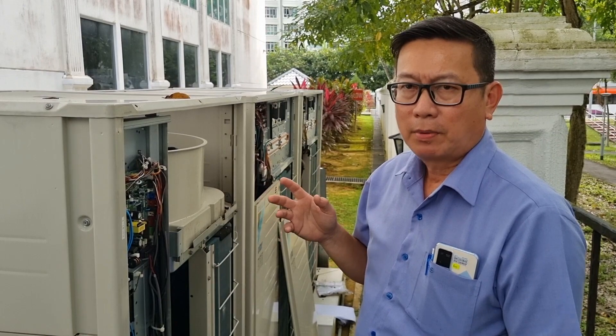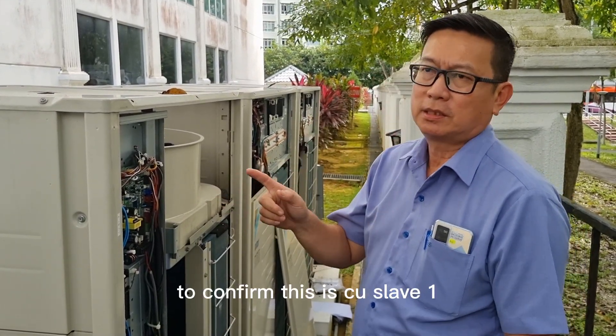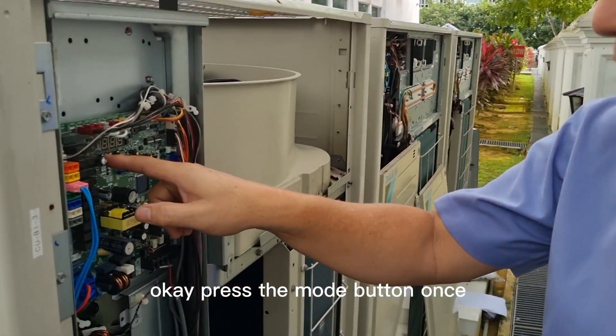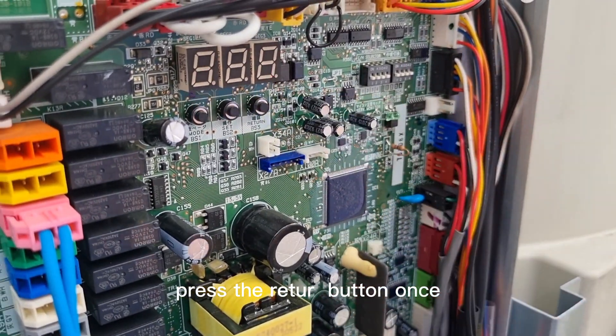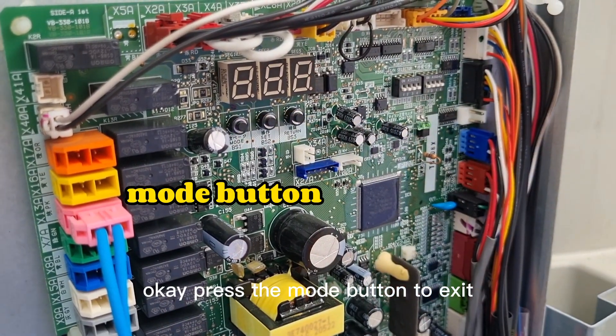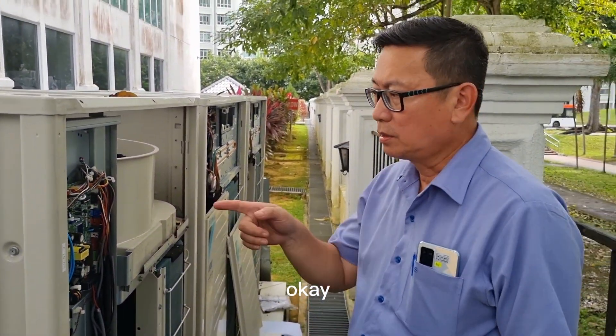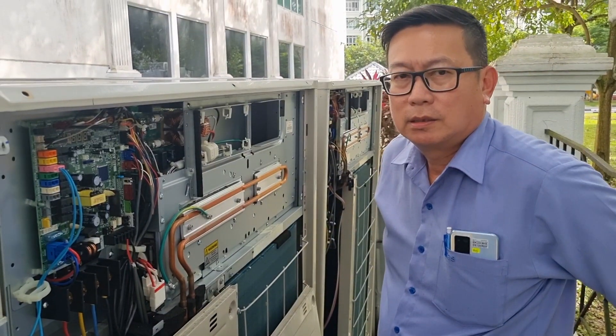That means Slave unit one has a power supply or communication error. Now we check to confirm this is Slave one. Press the mode button once, press the return button once. This is Slave one confirmed. Press mode button to exit. So, PJ-05...